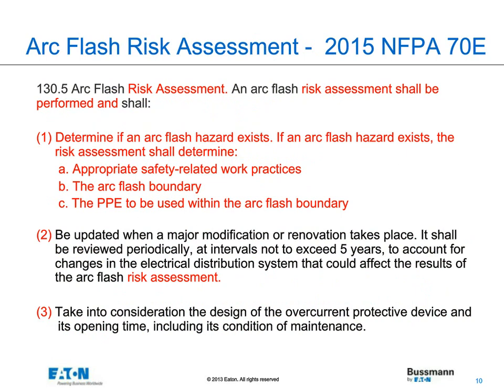Moving into the arc flash risk assessment, here we have, I used to say arc flash hazard analysis. Now the term is referred to as an arc flash risk assessment. It talks about the basic things you have to do for that. So there's a new one, and that's been put in from a text to a list item mode. But basically we have to identify the safe work practices, the arc flash boundary, and the PPE to be used within the arc flash boundary.